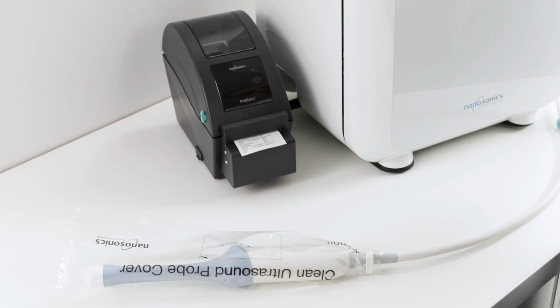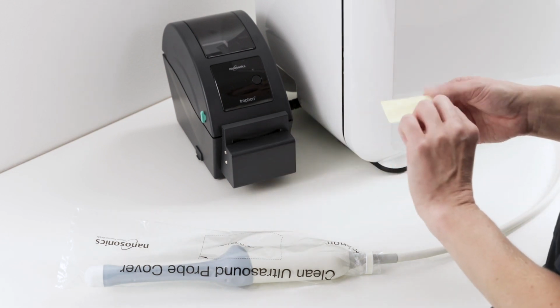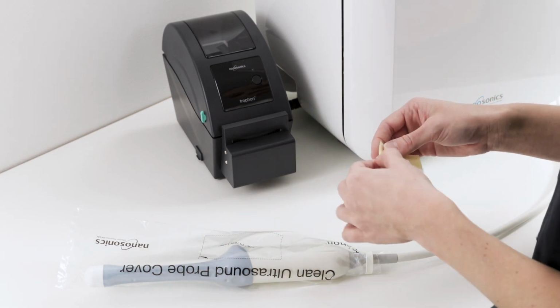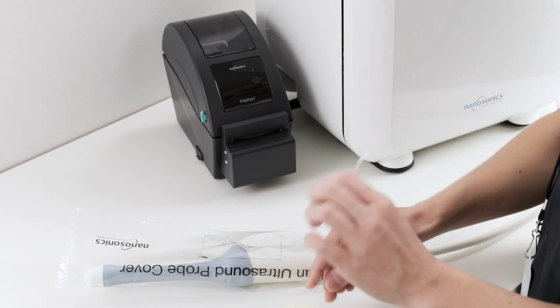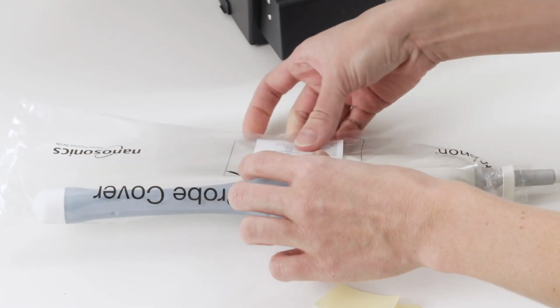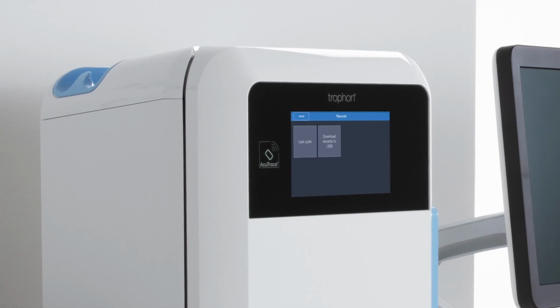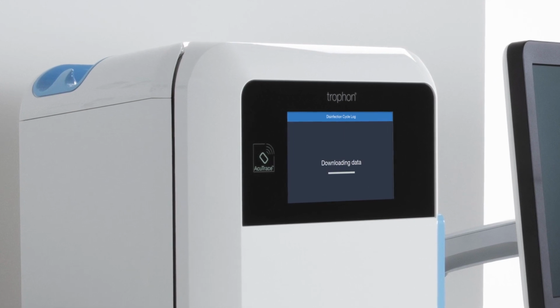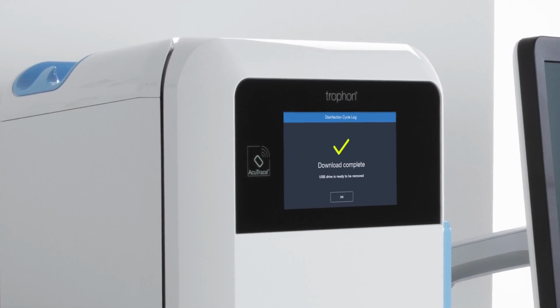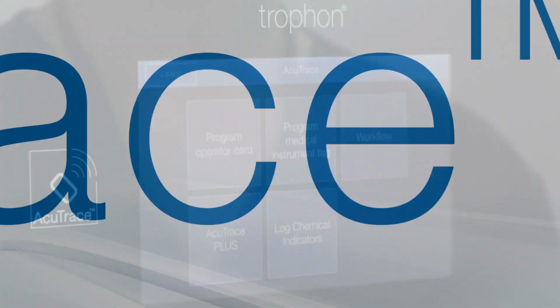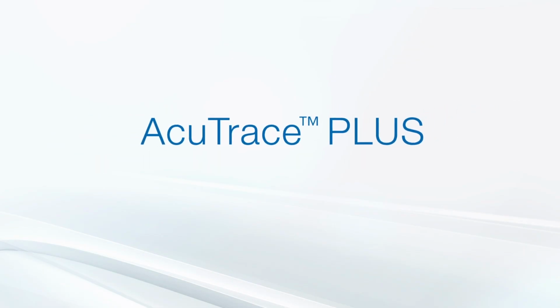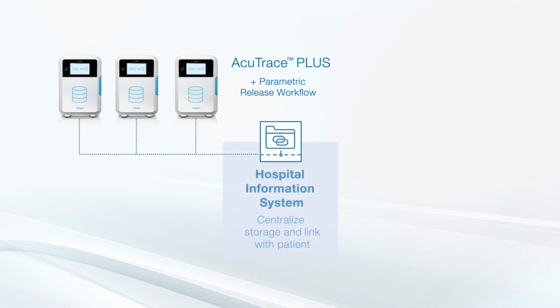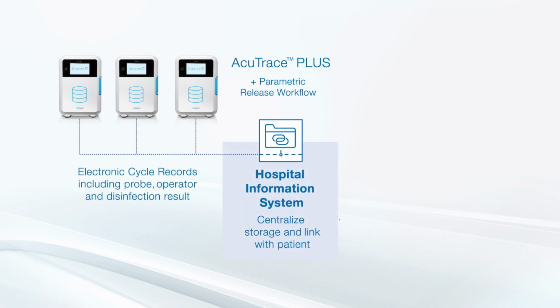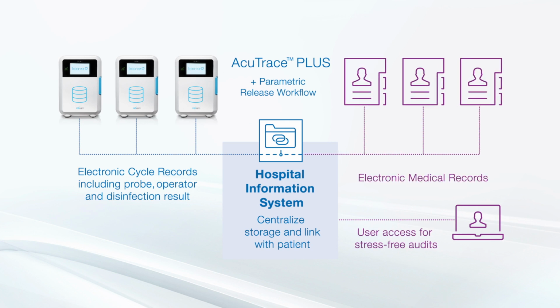If you have the trophon printer installed, information on the disinfection cycle can be automatically printed out on up to 4 labels. One printed label can be placed on the trophon clean ultrasound probe cover or in the patient's medical record for traceability. Alternatively, the disinfection records can be downloaded onto a USB for record keeping. If you have activated the optional AcuTrace PLUS software, your trophon2 can be integrated with the hospital IT system, allowing all disinfection cycles to be stored and accessed and easily linked to a patient's electronic medical record.